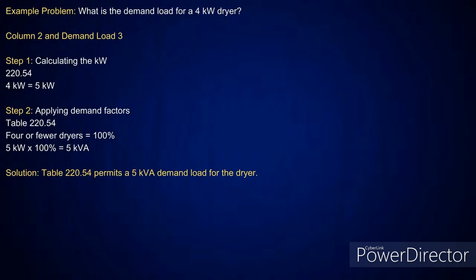Now, this gets very simple, because when you go over and you look at your dryer load, one thing that we definitely know here is that it has to be rated at what? 5,000 watts. Right. Okay? So no matter what, I'm going to have to kick this up to 5 kW. And if you go look at 220.54, it's going to tell you that. Now, if I have 1 to 4 dryers, you look at table 220.54 and you're going to take it at 100%. Once you start getting above that level, then there's demand factors that are going to be applied there for your percentage.